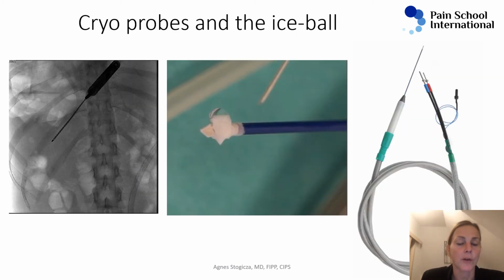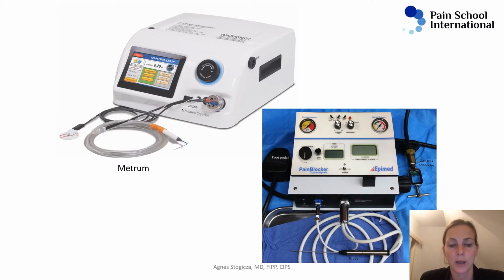This is how the cryo probe looks. This is the whole gear that plugs into the machine. This is the ice ball. You can see I was dripping lidocaine on the tip of the cryo probe, and you can see that there's an insulated shaft, and the tip is where the freezing happens. And I put this here so you see the size of it. It's a relatively big probe, which has some implications when you do the procedure. These are the machines that the probe plugs into, and there are other companies in the market as well.